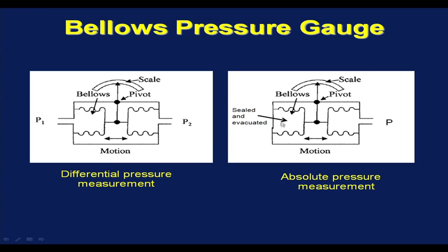If I seal one of these bellows and it is evacuated, so there is zero pressure inside, in that case the bellows element will measure absolute pressure. So, to measure absolute pressure with the help of a bellows, one of these bellows will be evacuated completely and sealed, so that it has zero absolute pressure. In that case the pressure that is being applied here will have a reference against zero absolute pressure. In other words, we can measure absolute pressure.